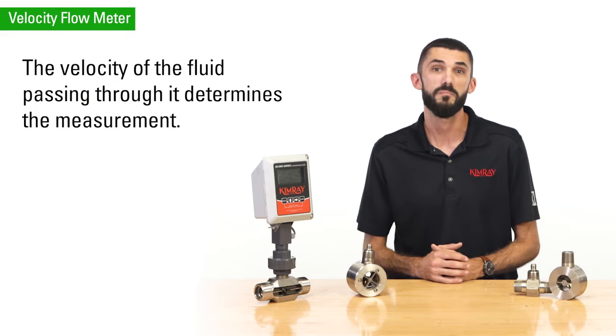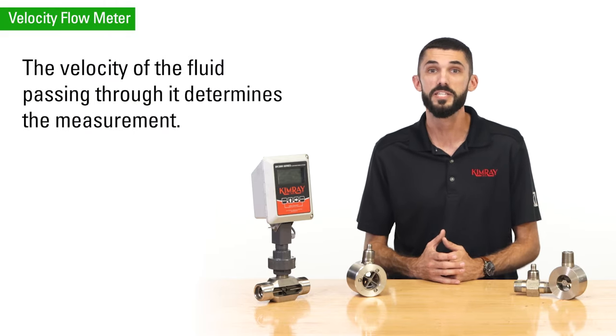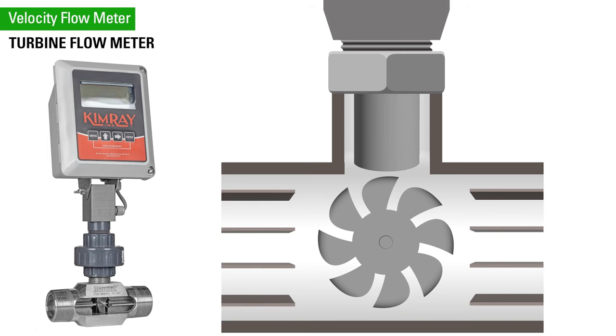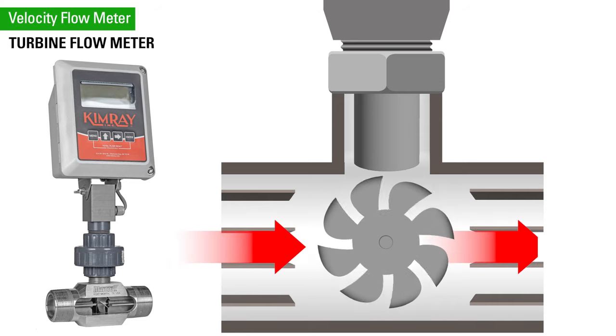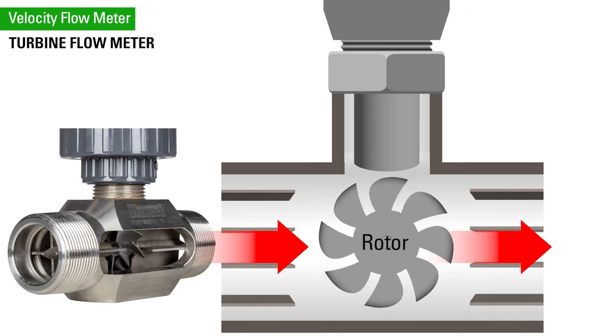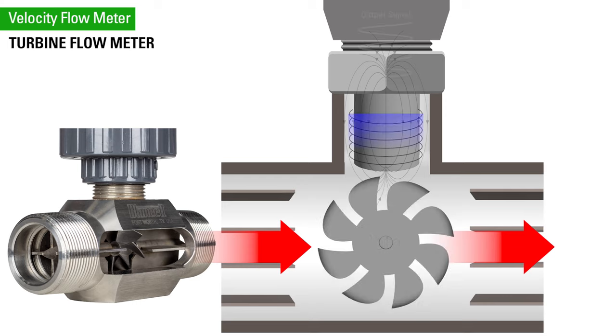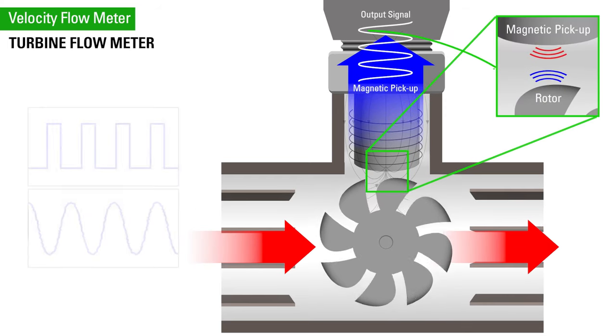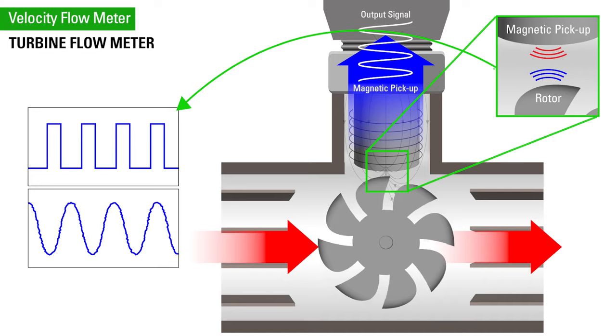The next type of flow meter we'll talk about is a velocity meter. With this type of meter, the velocity of the fluid passing through it determines the measurement. The most common velocity meter is a turbine flow meter, which calculates flow based on the fluid flowing through a free-spinning rotor. Each revolution of the rotor is read by the magnetic pickup and corresponds to a specific volume of gas or liquid.